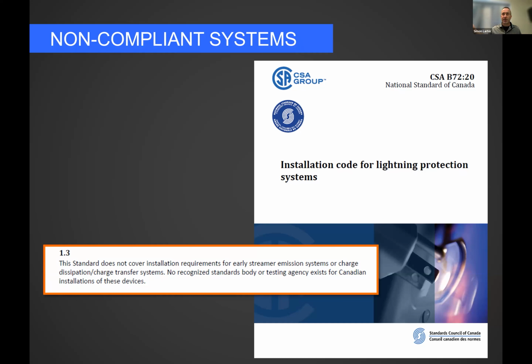We have to put our own bonds on there, unless all the grounding is put together on a main ground bus, then we are permitted to make a single connection to the main ground bus. But the way the code is written, we have to use lightning conductor and lightning fittings to make those bonding connections. So functionally speaking, we should be making sure we bond it with our conductors, our fittings. And is it redundant? Yes, it kind of is. But that's how we do our quality control, to make sure that we are absolutely connected up the way we should be.